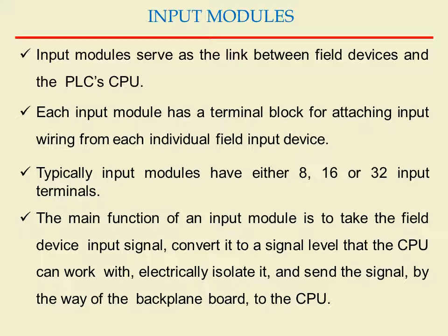The main function of an input module is to take the field device input signal, convert it to a signal level that the CPU can work with, electrically isolate it, and send the signal by way of the backplane board to the CPU. So basically, to connect the input devices to the CPU of PLC, input modules are used.